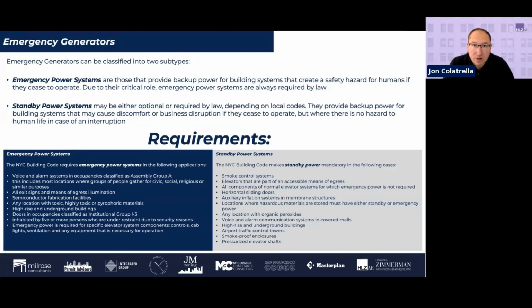The difference between an emergency power system and a standby power system, putting aside what needs to be connected, is the amount of time it takes the generator to transfer the loads. A truly classified emergency generator has to transfer all electrical loads within 10 seconds of the power going out from Con Edison. A standby generator, different, has to transfer the loads within 60 seconds. So it's quite a bit of difference, from the equipment to the design.